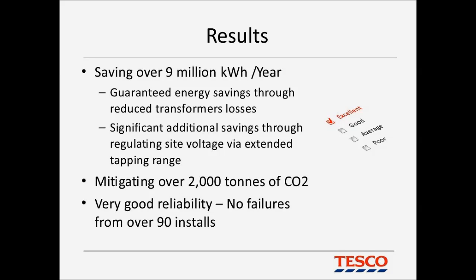So, the results. We're currently saving over 9 million kilowatt hours per annum. Now this figure is made up of obviously improved core losses, but also the ability to fine-tune the voltage setting because of the extended tap range available on the E2. This in turn is saving us over 2,000 tonnes of CO2 per annum. And from a reliability perspective, no failures. Of the 90 E2s installed, we've had no issues.